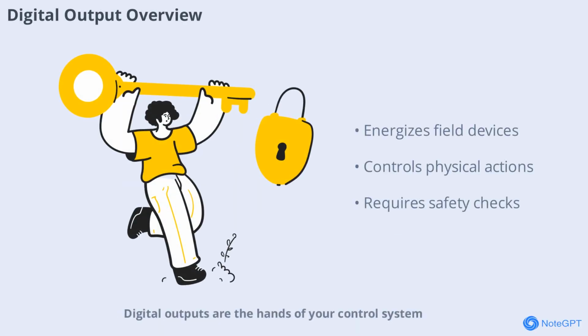Digital outputs are the hands of your control system, sending 24 VDC signals to energize field devices like motor contactors, solenoid valves, or horns. These outputs directly control physical actions in the plant, making their verification critical for safe and effective operation. For testing, safety precautions must be taken to ensure that the equipment is clear and safe to operate. Let's explore the basics of digital output and why proper verification is essential.